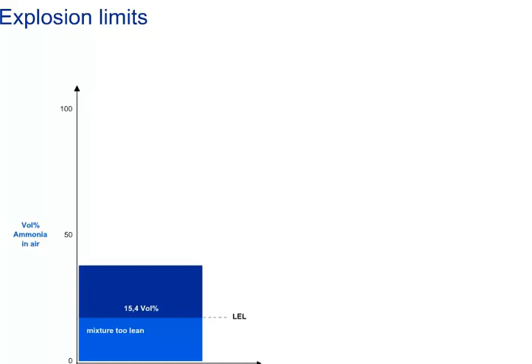Now let's look at 3 examples which will show how dangerous some gases are when they're mixed with air. If you mix ammonia with air, the lower explosion limit, LEL, starts at about 15 volume%, and the upper limit will be reached at 33.6 volume%. After that, the mixture is too rich to create an explosion, but there is still the risk of a fire hazard.